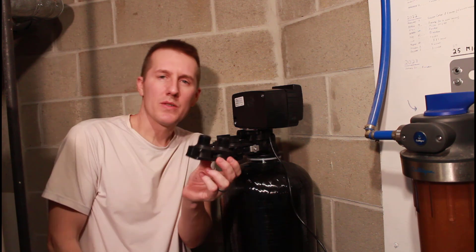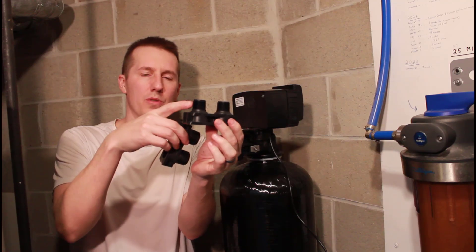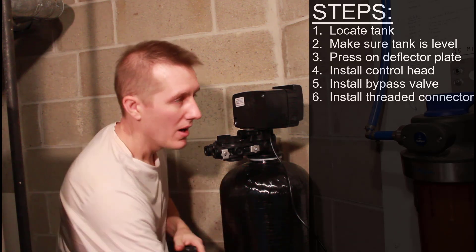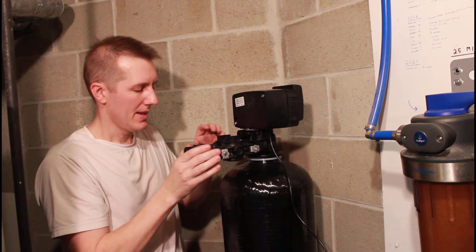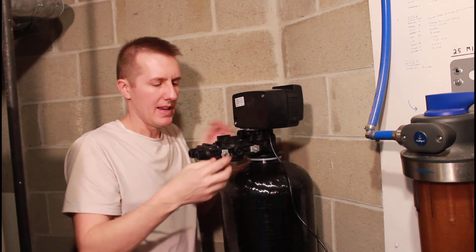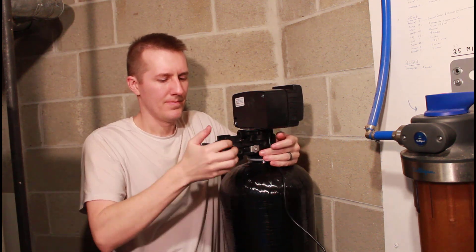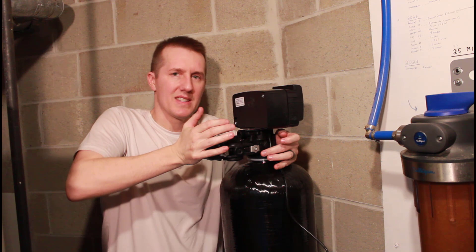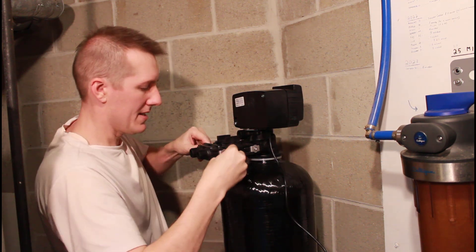The next part that goes on is this threaded yoke, it's called. And they give you two, three-quarter inch and one inch. Now, all my pipes are three-quarter inch, so that's what I'm going to be using. And this goes on the same way. Just pushes on, and then you tighten up these little metal clips on the end. Push it until it's nice and seated. And there's that O-ring in the middle. And then tighten the screws up.